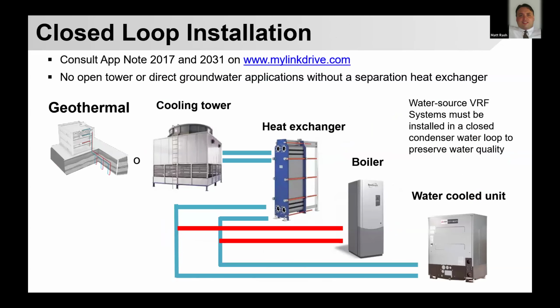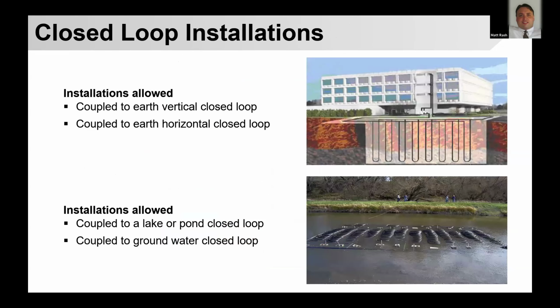As I mentioned, this product is rated for geothermal. It can often be applied with cooling towers and absorption with boilers where needed in hybrid strategies, but perfectly suitable for closed loop, and I'll highlight that, closed loop geothermal type applications. So vertical bore well fields, closed pond loops, perfectly fine. Anytime you get into a pump and dump type application, there has to be a separation with separation heat exchangers. We need a closed, chemically treated, sealed loop for these systems to operate with.